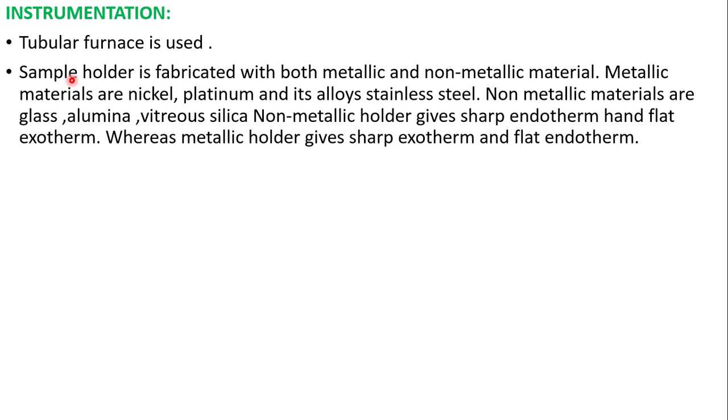Instrumentation. In the DTA technique, a tubular furnace is used. A sample holder is fabricated with both metallic and non-metallic materials. Metallic materials are nickel, platinum, and its alloys of stainless steel. Non-metallic materials are glass, alumina, vitreous silica, etc. A non-metallic holder gives a sharp endotherm and flat exotherm, whereas a metallic holder gives a sharp exotherm and flat endotherm.